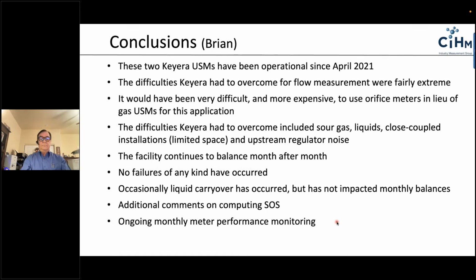Yep, so as part of our regular PMs and our measurement program to our producers, we do monthly checks on the speed of sound to verify meter performance. We have a multi platform of ultrasonic meters, and up in the Montney Basin we see a lot of contaminants in the gas. With the different transducer design on the RMGs, the transducers are not inside the flow path, they're recessed. What we're finding is they don't get fouled, even when they're dirty, and with the higher power, it seems to not affect them. So when we run our monthly checks on the SOS with our current gas composition, it's maintaining very steady, with not a lot of changes or error percentage found. It's almost pretty much month after month bang on the money, which is great.